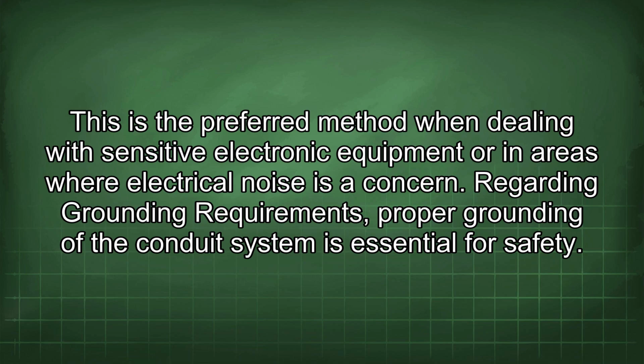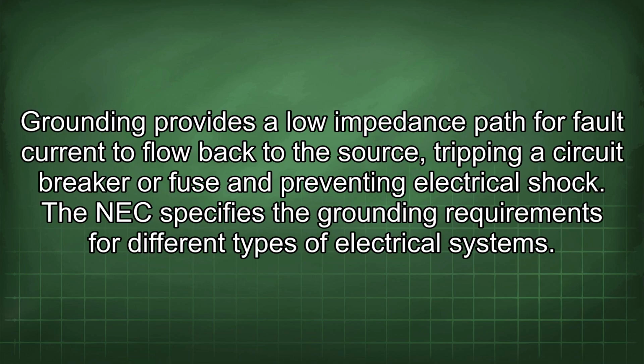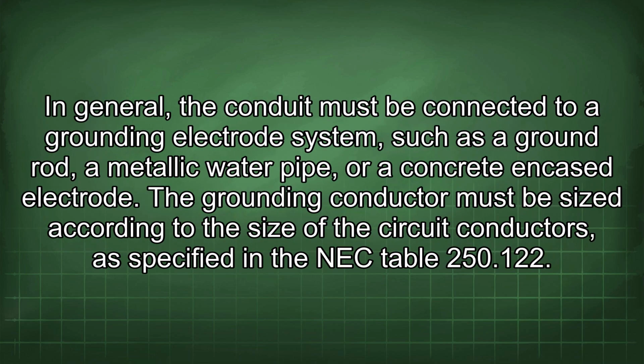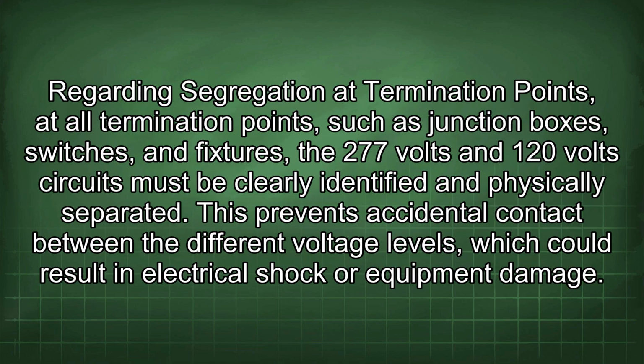Regarding grounding requirements, proper grounding of the conduit system is essential for safety. Grounding provides a low impedance path for fault current to flow back to the source, tripping a circuit breaker or fuse and preventing electrical shock. The NEC specifies the grounding requirements for different types of electrical systems. In general, the conduit must be connected to a grounding electrode system, such as a ground rod, a metallic water pipe, or a concrete encased electrode. The grounding conductor must be sized according to the size of the circuit conductors, as specified in NEC Table 250.122.